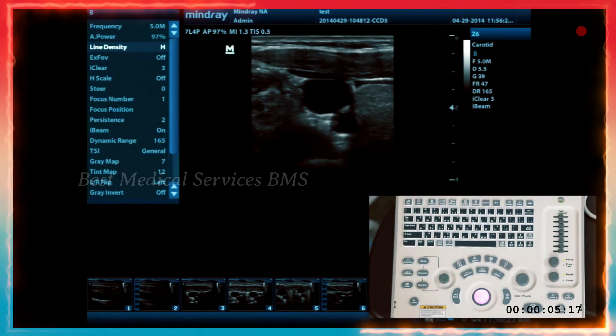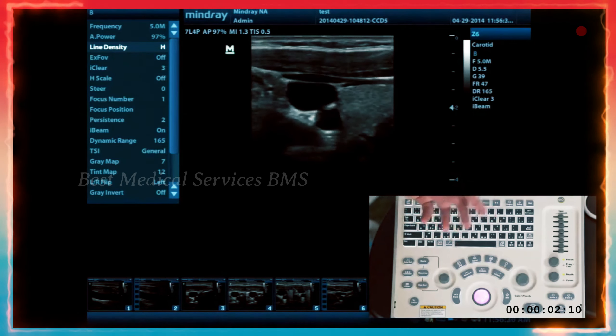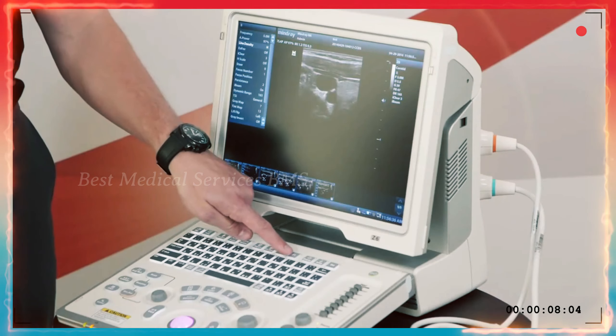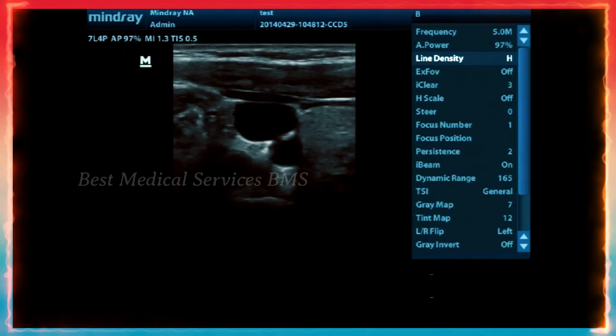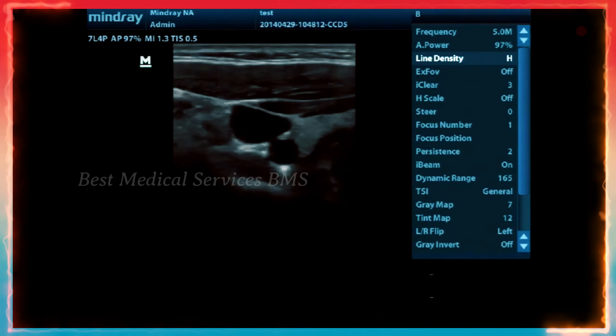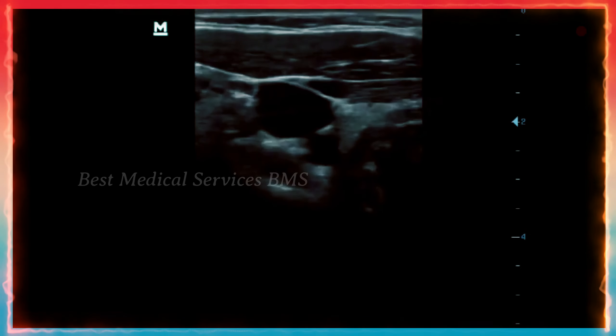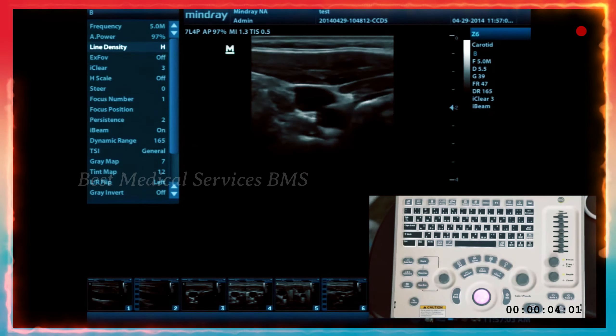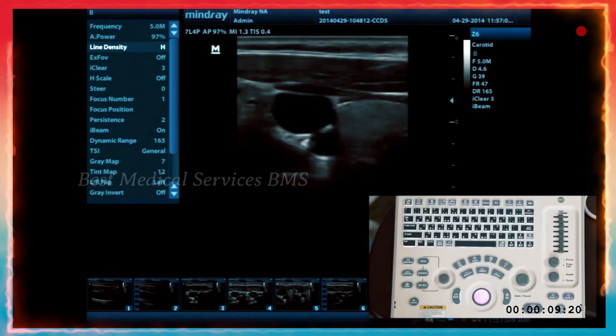The iZoom on the machine is called iZoom and is on the F1 key by default in your key configuration. F1 will actually be an iZoom — it up-samples the image so you're not zooming in and losing pixels; it keeps the image sharp. If you hit F1 again, you go full screen. You have the ability to go between normal size, medium, and a full up-sampled large screen. Press F1 again and it returns to normal view with saved images along the bottom and patient information on the banner.